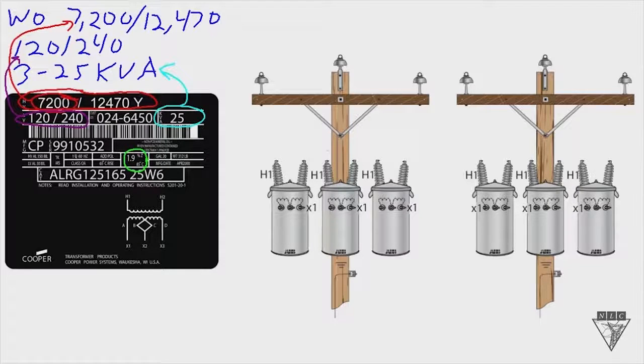So if we move over here and we look at our transformers on the bank here, let's say that we got 1.9% on this first one. And the second one we've got 1.9%. But let's say on this last one, we've only got 1%. The reason why this is important to try and get 3 transformers that the impedance is very close together is this one transformer over here that's at 1% is going to take on more of the load.